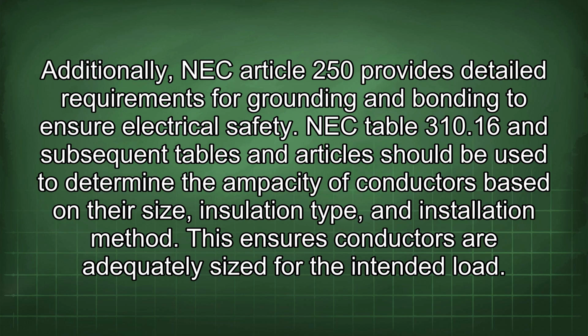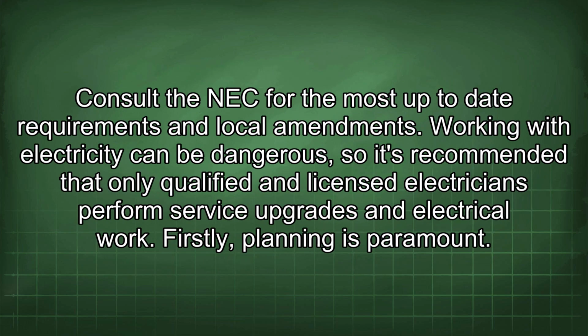NEC Table 310.16 and subsequent tables and articles should be used to determine the ampacity of conductors based on their size, insulation type, and installation method. This ensures conductors are adequately sized for the intended load. Consult the NEC for the most up-to-date requirements and local amendments. Working with electricity can be dangerous, so it's recommended that only qualified and licensed electricians perform service upgrades and electrical work.